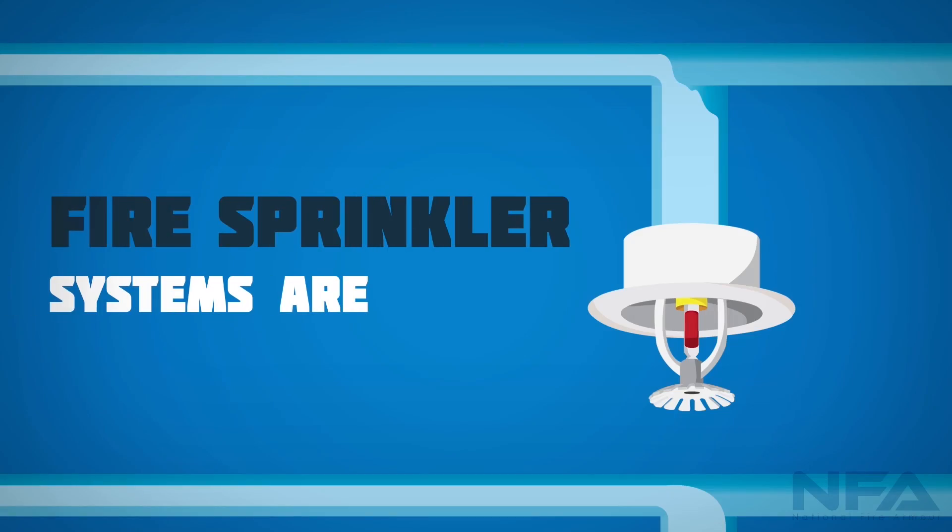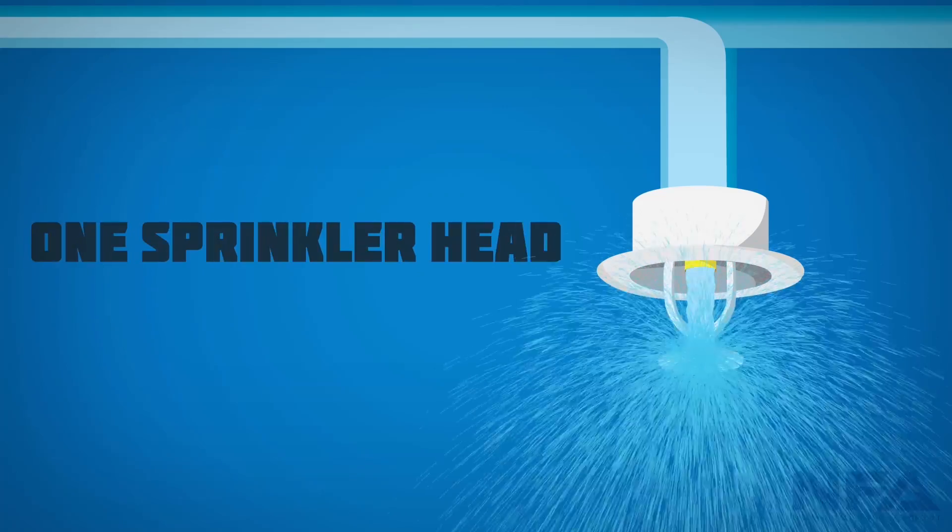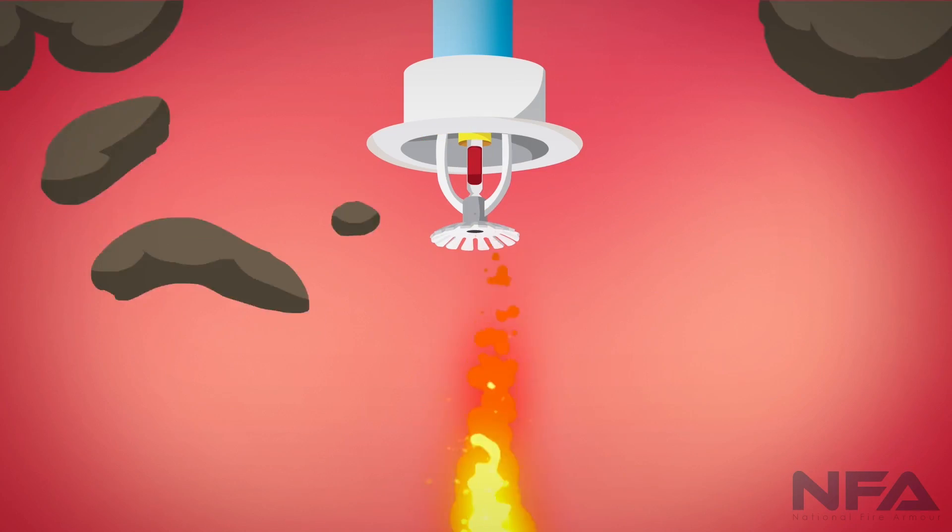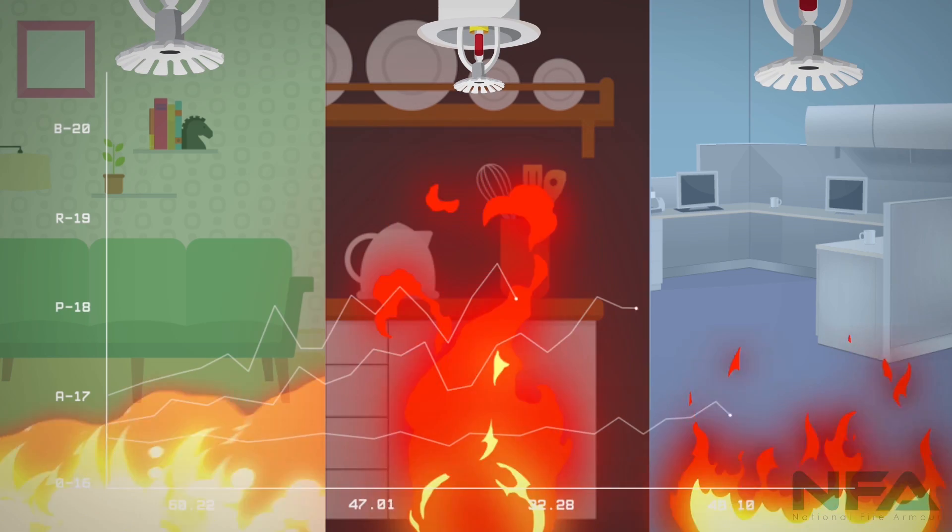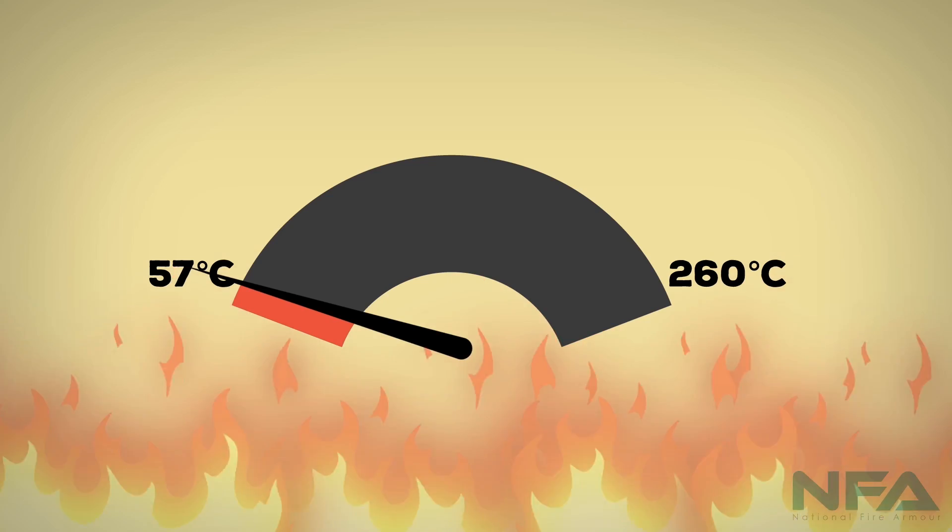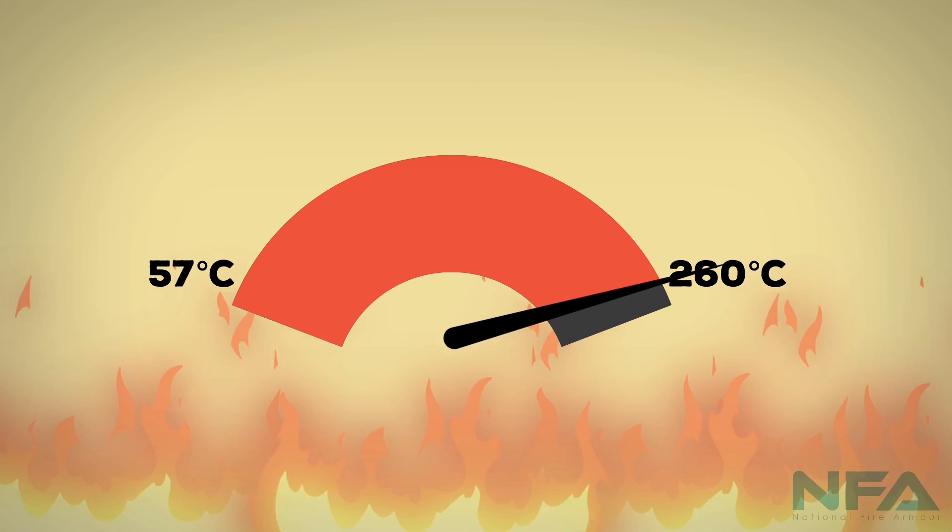Fire sprinkler systems are heat activated one sprinkler head at a time. The sprinkler head must detect a high enough temperature. Usually, there are different temperature ranges for sprinklers, starting from 57 degrees centigrade to 260 degrees centigrade, depending on the hazards.